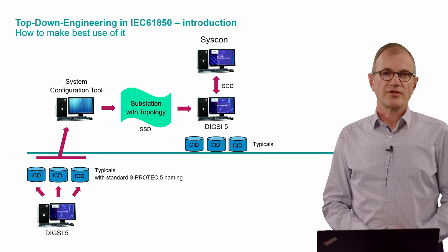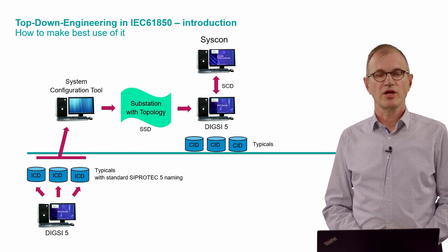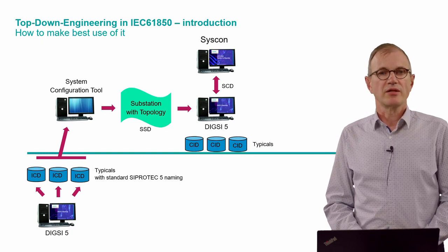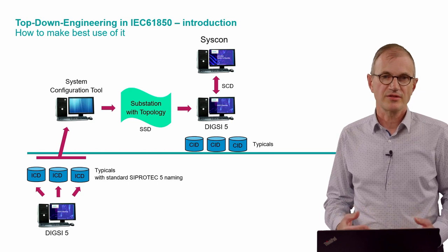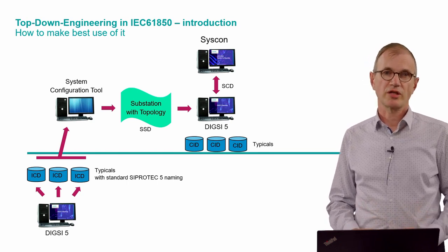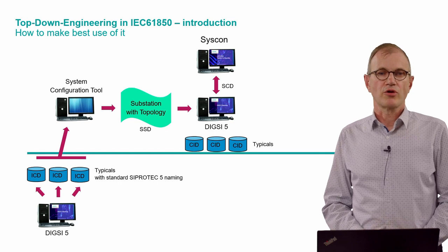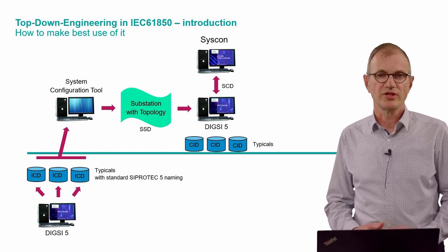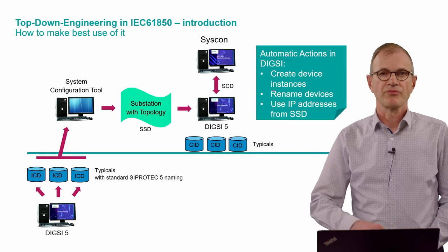This SSD file is then imported to DIGSI 5. This is the new functionality we have implemented last year. And then you can create the substation instance from that project. You can have the normal exchange of the SCD file with the syscon, and you then have the configured IED descriptions, the CID files, which can then be downloaded to the devices.